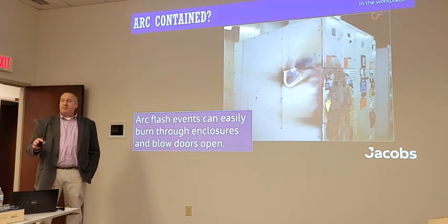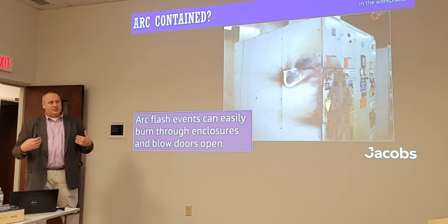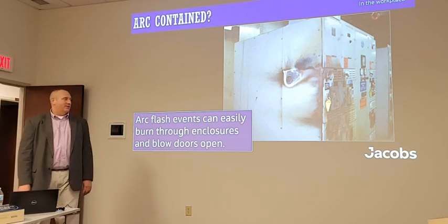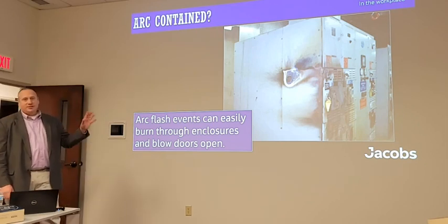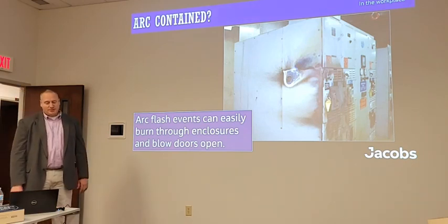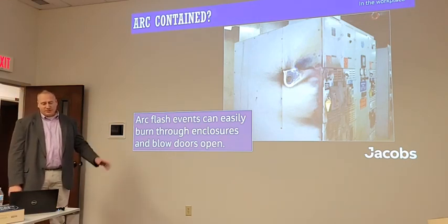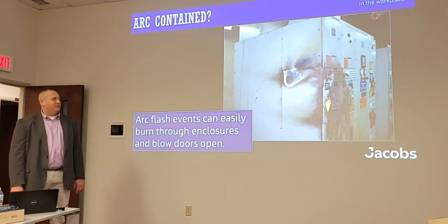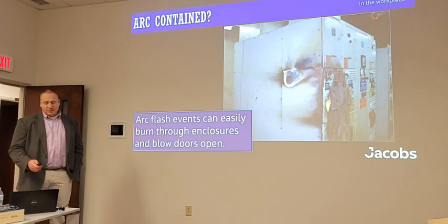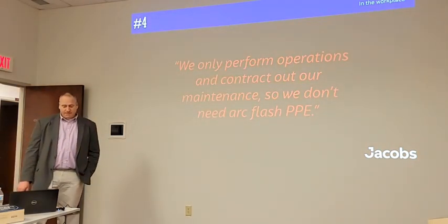But the thing to keep in mind with arc-rated gear is, at least all the styles that I've seen to date, it's only arc-rated for normal operations. Once you open it up to do maintenance or do anything to it, opening those doors defeats that arc-rated characteristic. You've got to treat it just like normal switchgear. So just having the doors closed is not the case. We've got to wear proper arc flash PPE.